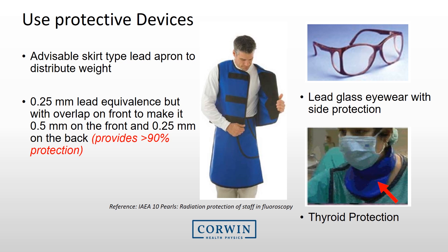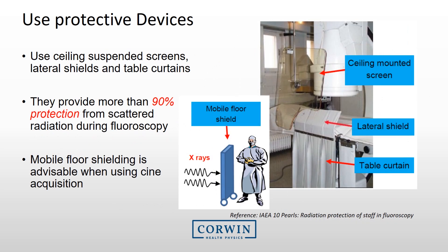Using just 0.25 mm lead provides more than 90% protection from scattered radiation. In addition to personal lead, use ceiling suspended screens, lateral shields, and table curtains — they too provide more than 90% protection from scattered radiation. When available, it is recommended that a mobile floor shield be used during cine runs or digital acquisitions.